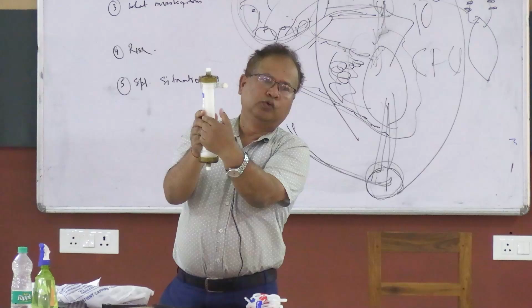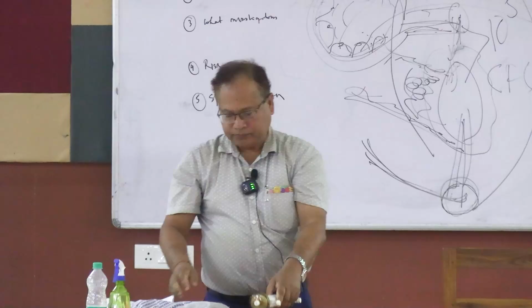After passing through these capillary tubes, the blood goes out through this tube and enters the patient's body. One tubing takes the blood into the dialyzer and it goes out from this tubing and enters the patient's body, as simple as that. And through the effect of the machine, a negative concentration gradient and a negative pressure gradient is maintained, so that fluid and solutes are dragged from inside the capillary tube to the dialyzed fluid.